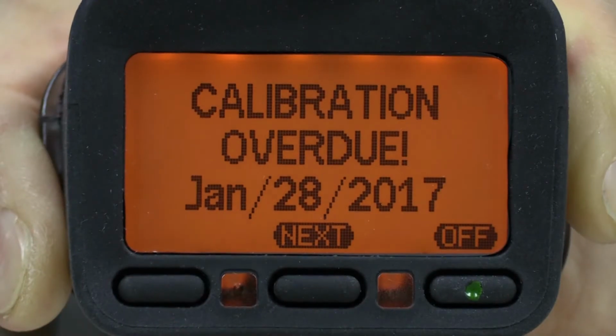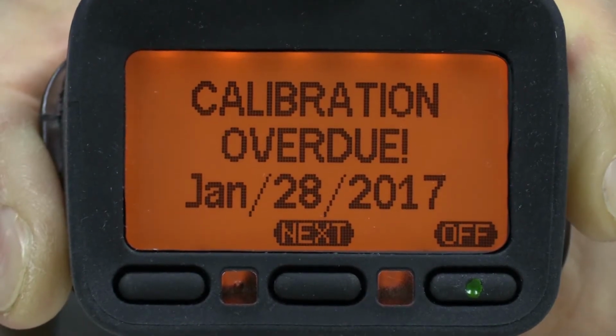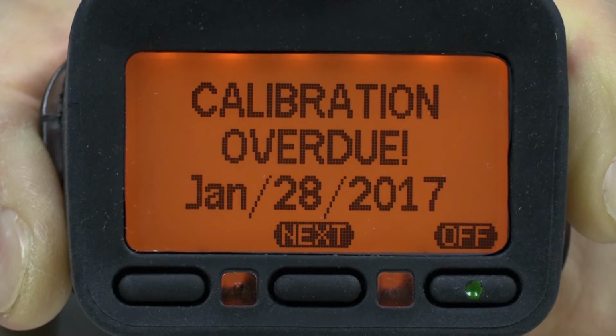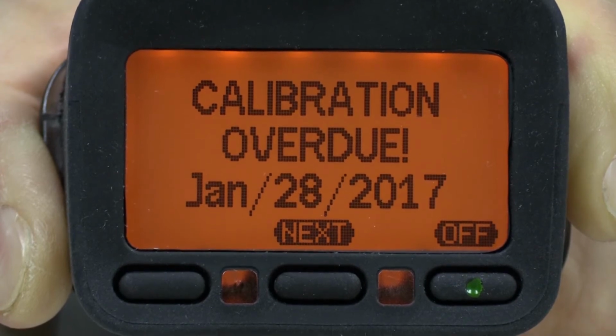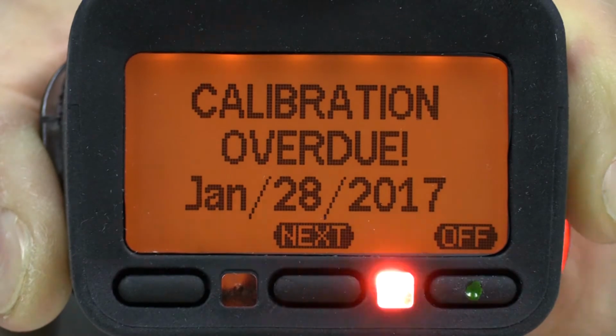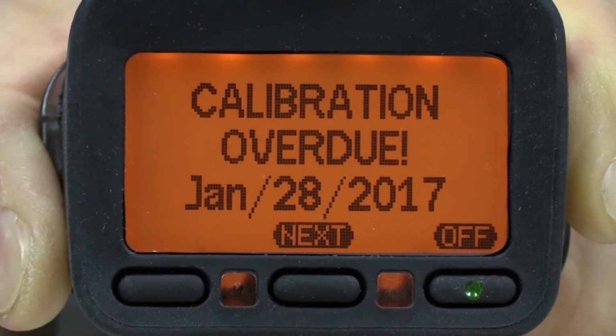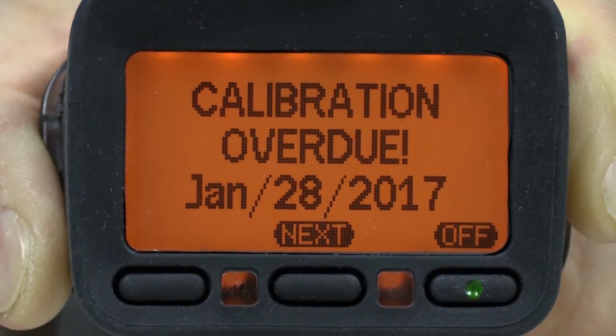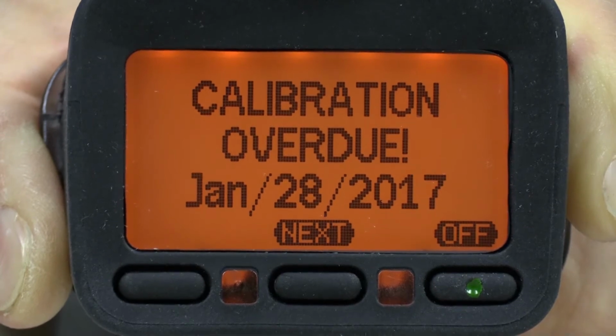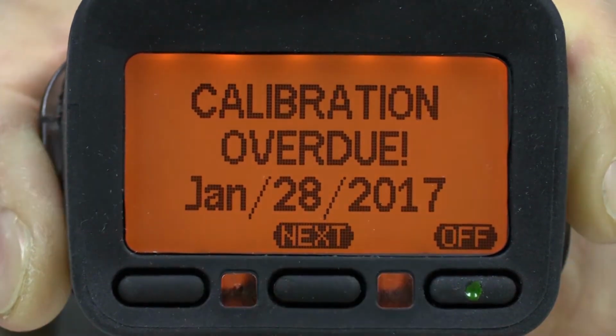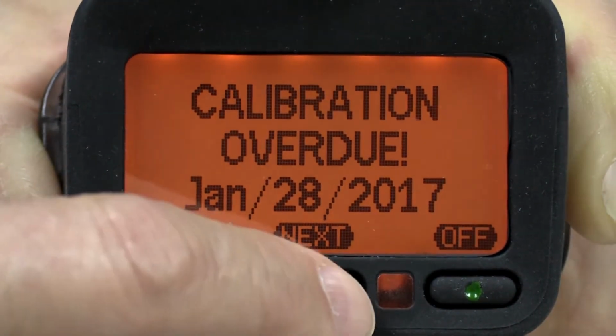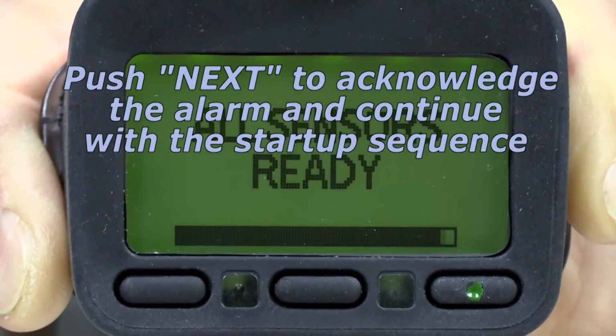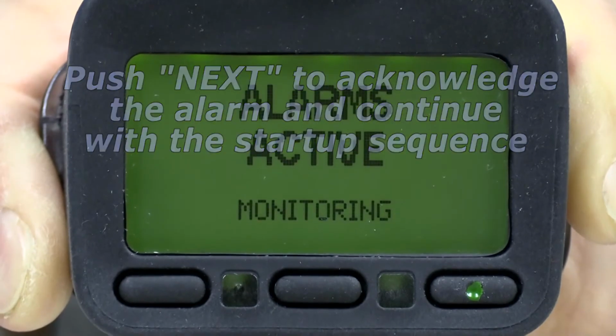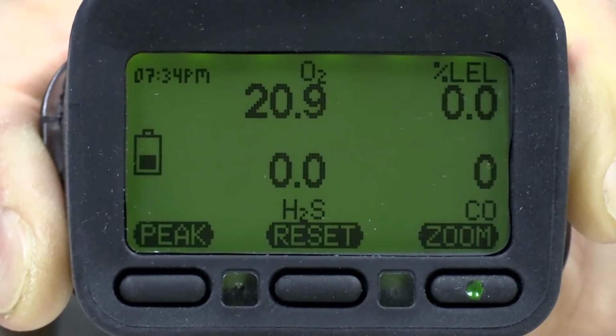on. During the startup sequence, the G450 will sound an alarm and display a notification message if the instrument is overdue for a bump test, overdue for a calibration, an inspection, if the battery pack is depleted, or if there is a problem with one of the sensors. If a bump test overdue or a calibration overdue message is displayed, push the Next button to acknowledge and silence the alarm. Be sure to complete the required procedure before going on to use the instrument in normal operation.